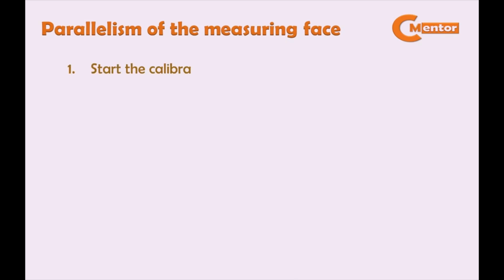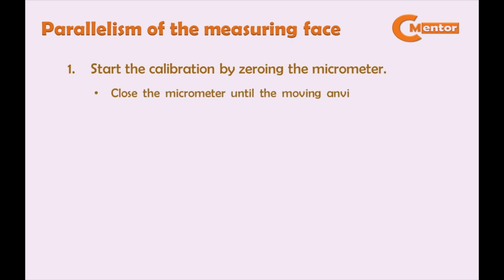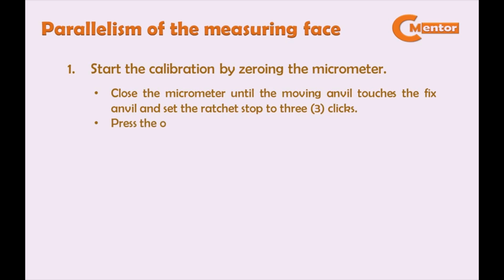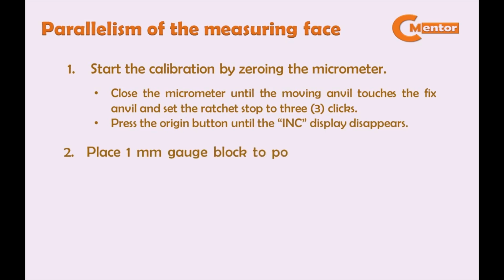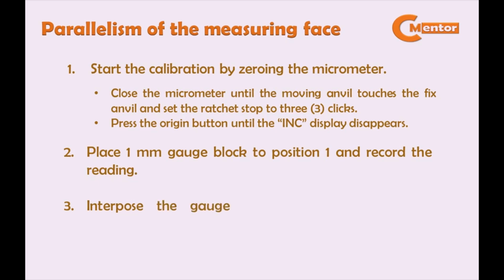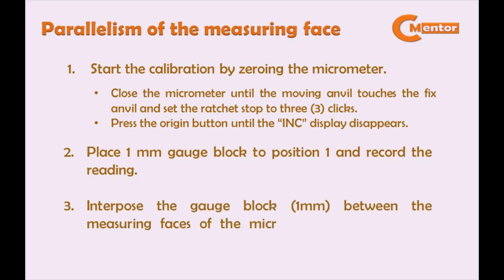First, start the calibration by zeroing the micrometer. Close the micrometer until the moving anvil touches the fixed anvil and set the ratchet stop to 3 clicks. Press the origin button until the INC display disappears. Second, place 1 mm gauge block to position 1 and record the reading. Third, interpose the gauge block 1 mm between the measuring faces of the micrometer and record the readings.